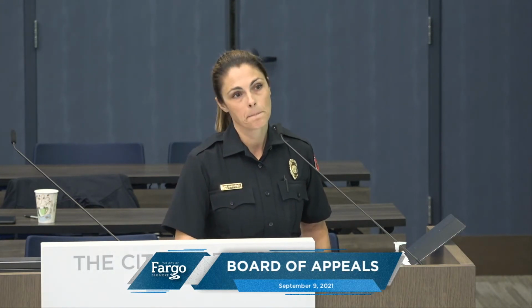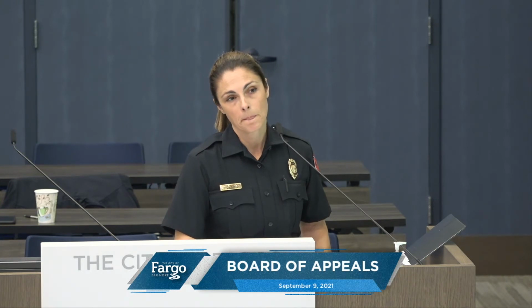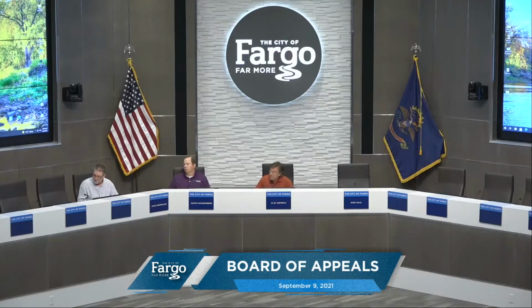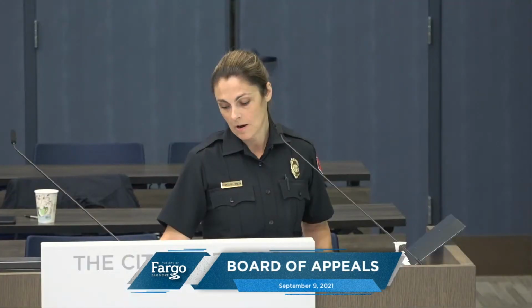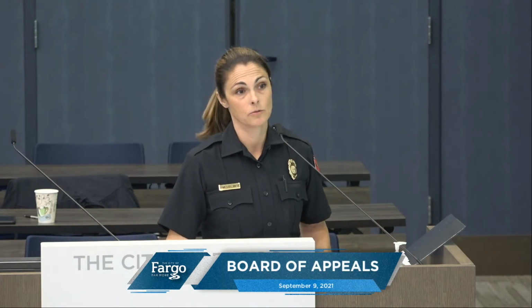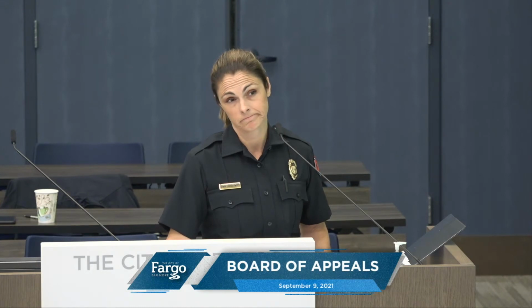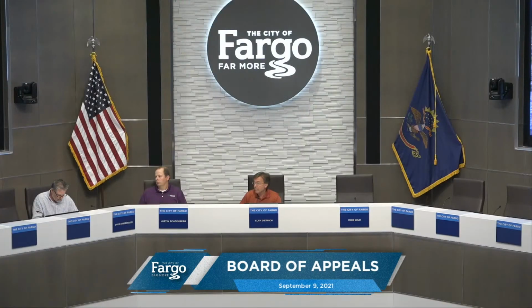Is this independent of the size of the building or square footage of the building? The way it states is it's required throughout the S1 area used for the bulk storage of wines and distilled spirits. So I'm just wondering about the F1 distilled spirits and the S1 distilled spirits and wines, Group 1 fire. I'm just wondering if, say, somebody has a 1,000 square foot, they have to put a sprinkler system in?